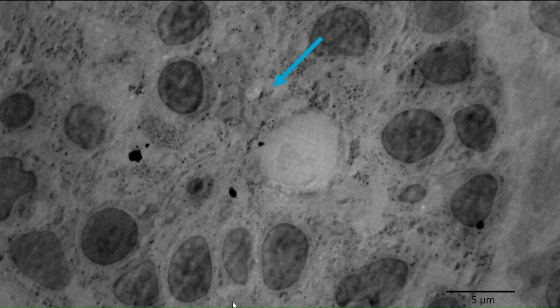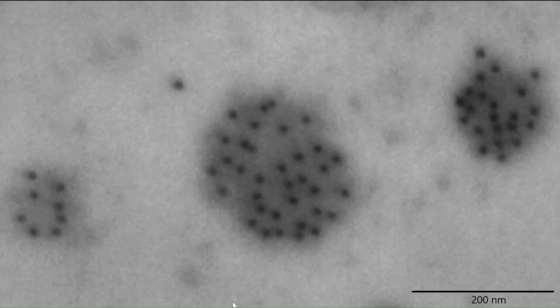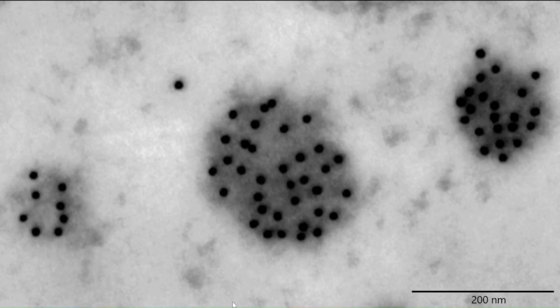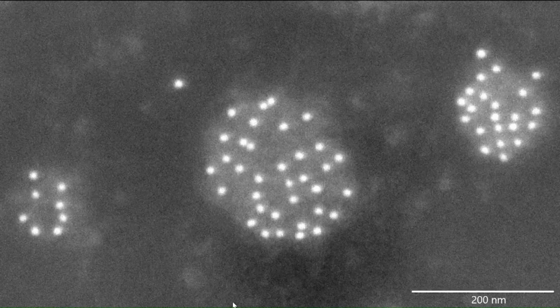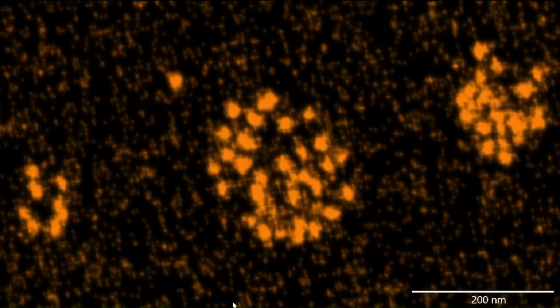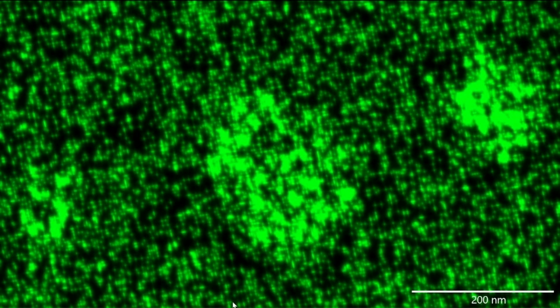So, during one imaging session, we can easily get a quick sample overview in TEM and quickly find the point of interest. Improve the contrast and resolution of this thicker sample in STEM. Check the metallic character of nanoparticles in SEM with backscattered electrons. And verify in EDS that the metal is gold and that the gold is bound to insulin, which has a high share of sulfur. And we can also add electron diffraction, all from one sample, one device, and one time slot of about 1 hour.